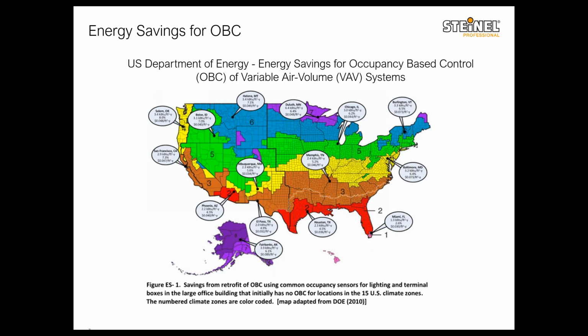But one of the interesting pieces of information that I saw was that in a typical school, since we are quite involved with school projects, like most of you, about 58% of the energy consumption is from the HVAC system. I mean, it's not all electrical. Parts of it, the heating part, would be gas, but still a huge portion of it would be from cooling and ventilation, which if combined with occupancy would give a very good energy saving, especially cooling that you need in summer when school is mostly closed. So you don't want to be constantly cooling down an empty school. You would only be cooling down based on presence of students or staff or someone in the school.